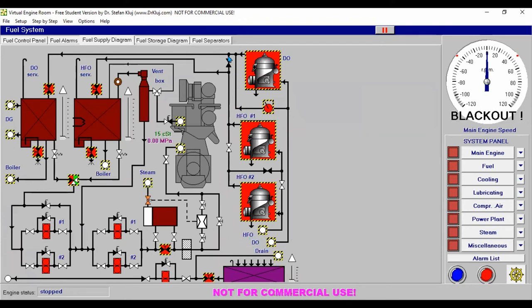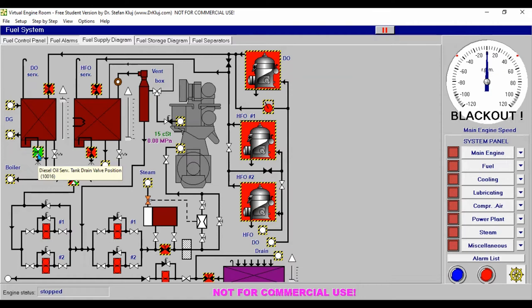Then at our diesel oil service tank, open it and we have to manually pump. You can see the level is rising. Once it reaches the required level, we stop the pump and close the valve. We also need to drain the water content to avoid failure to start our engine.